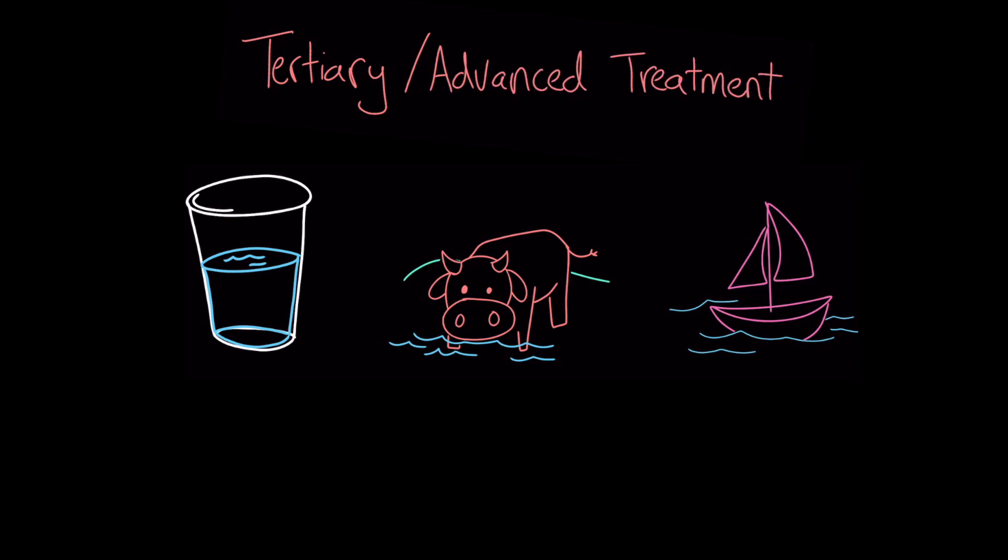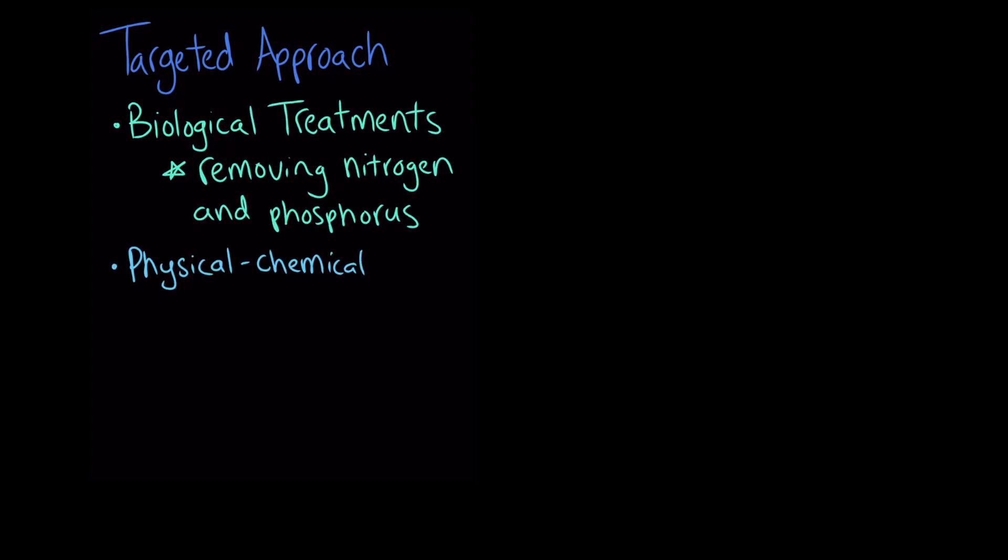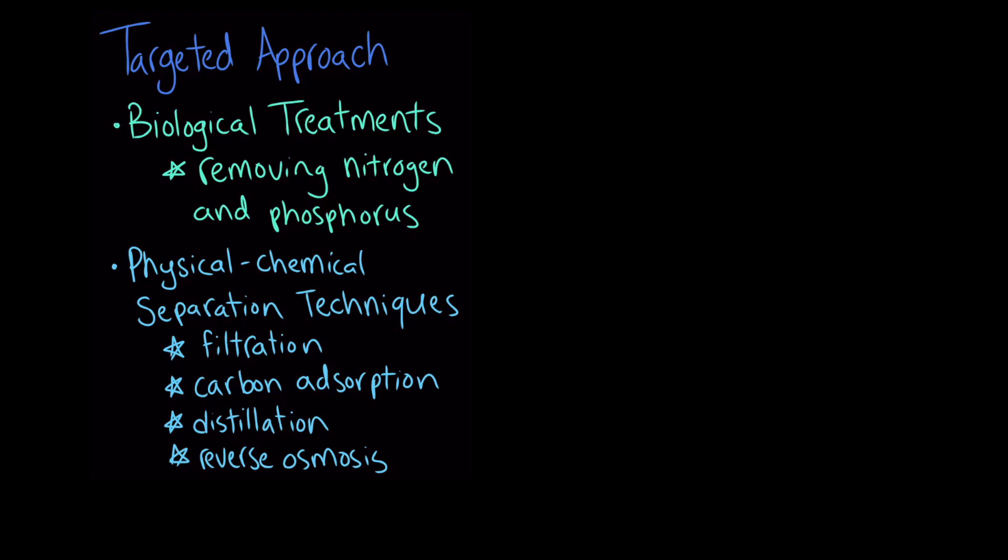Tertiary treatment looks different at different water treatment plants. Sometimes, it uses a more targeted approach to the removal of specific wastewater components. Some examples include additional biological treatments capable of removing nitrogen and phosphorus, or physical chemical separation techniques such as filtration, carbon adsorption, distillation, and reverse osmosis for removing a variety of chemicals.